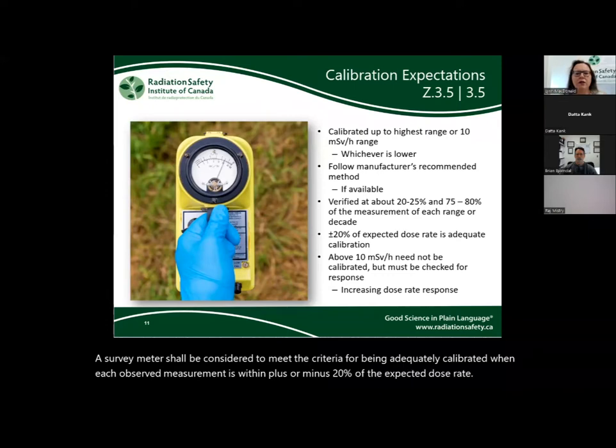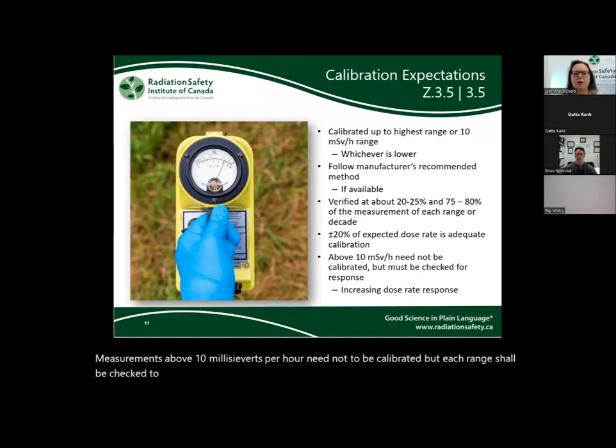Measurements above 10 millisieverts per hour need not be calibrated, but each range shall be checked to ensure response, and as far as practicable, by decreasing calibration distance, the appropriate increasing dose rate response shall be checked.